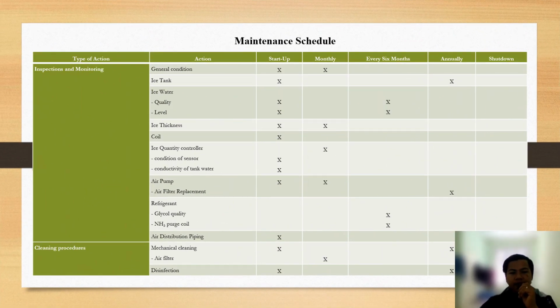This slide shows the maintenance schedule for ice storage units. The first one is type of action, inspection and monitoring. For example, general condition needs to be checked every startup and monthly. For the ice thickness, it needs to be checked every startup and monthly. For the cleaning procedure, for example mechanical cleaning, the air filter needs to be checked or maintained monthly or annually. For the disinfection, it needs to be done every startup or annually.